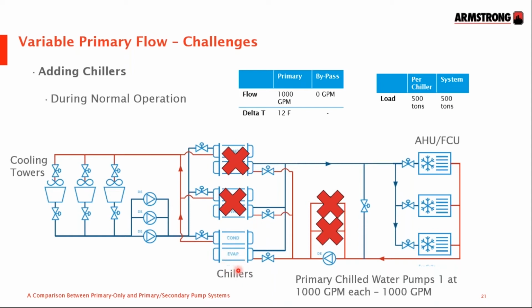So with half the flow rate and the same amount of cooling, the delta T, the drop in temperature, is going to go from 12 degrees to 24 degrees. So the return temperature is going to drop from 56 less 24 down to 32 degrees, freezing. As it happens, the low water temperature cutout will kick the chiller off once it hits 40 degrees Fahrenheit on those systems. So you end up with the chiller tripping out when you're trying to start a chiller, which is not a good thing. The solution is to use a valve here which modulates to open slowly over 1.5 to 2 minutes, so that the inlet vanes on the chiller compressors can keep up and start the second chiller without a hitch.